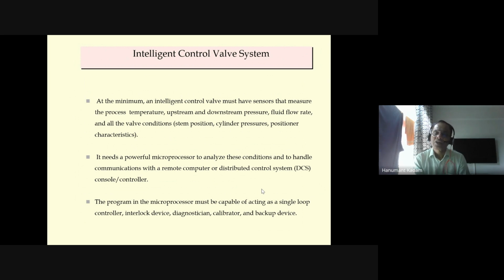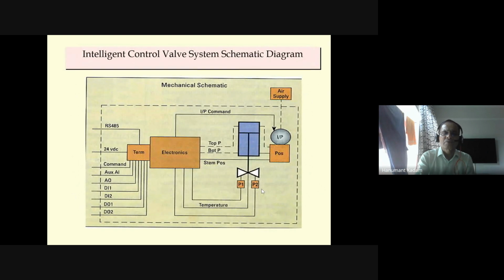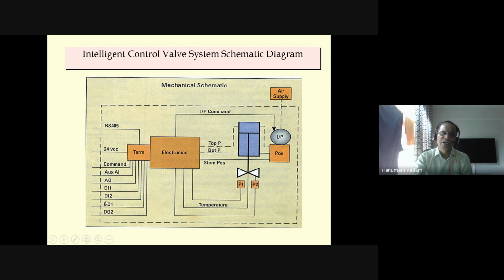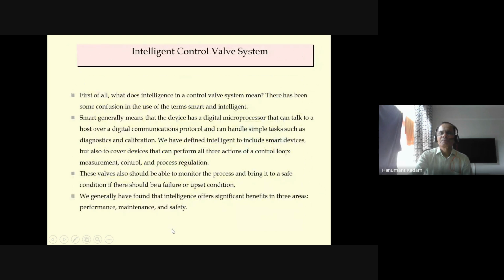It acts as a single loop controller, meaning a PID controller, interlock device, diagnostics, calibrator, and backup services. So all these functions are incorporated in these valves. You can see in the diagram again the interface with the DCS, Modbus. Then with these signals, DI, DO, AI, AO are there. You can have a safety interlock to be developed.